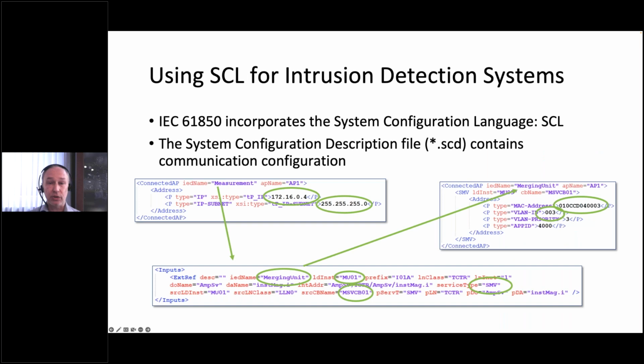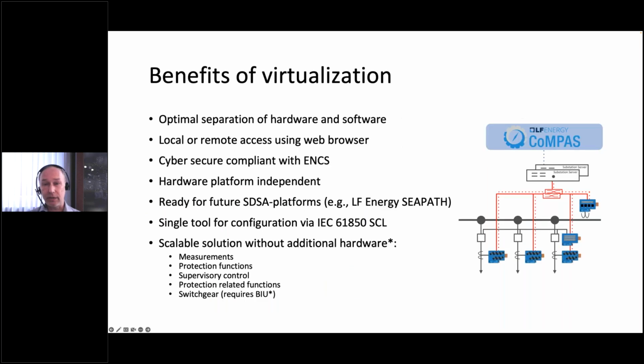Also, redundancy is easily achieved. You can add a second substation server, and if redundancy in terms of different protection algorithms is needed, this can be achieved by choosing a second vendor. Also, adding additional traditional IEDs is possible, as in the end, all equipment exchanges information by standardized communication as defined by 61850.